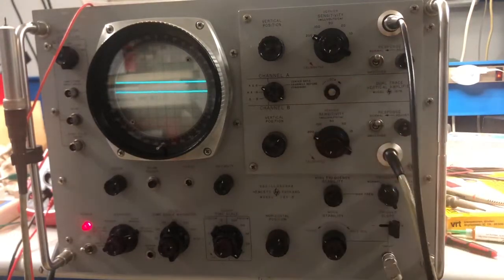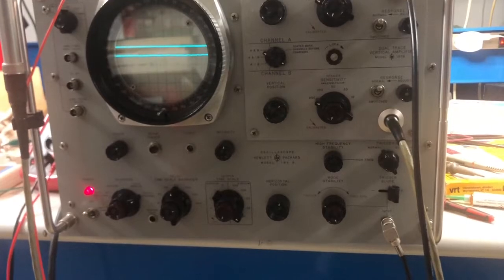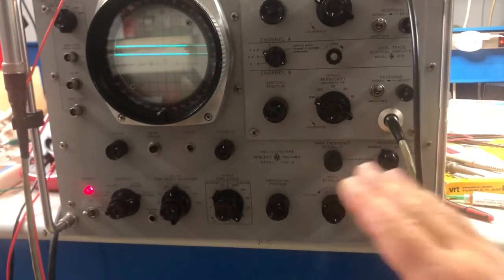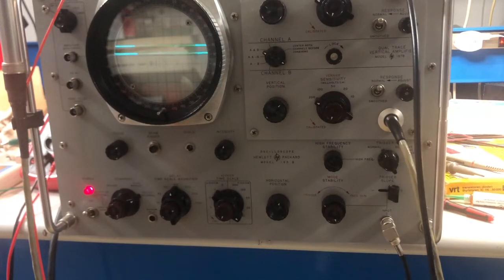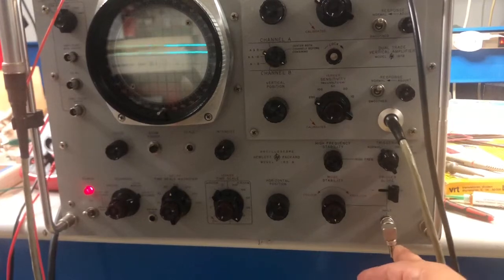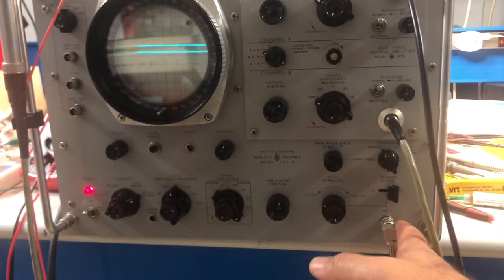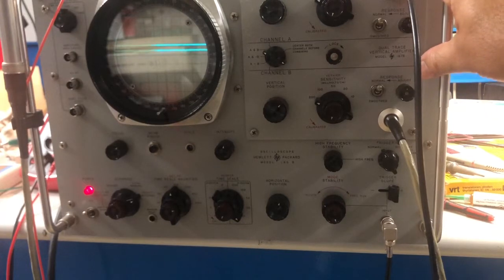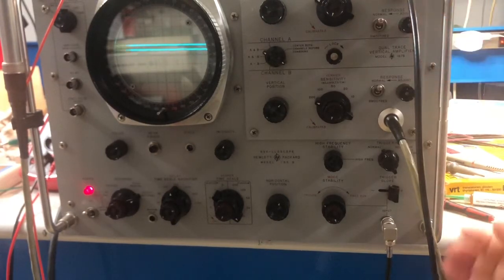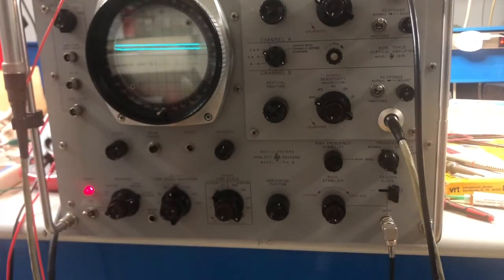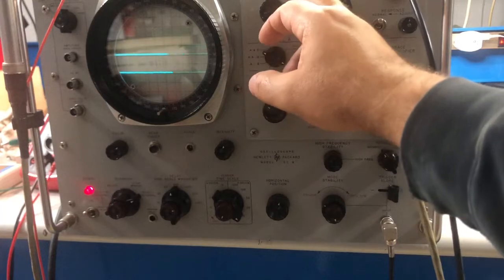Well, the way this oscilloscope works, it's not like a standard oscilloscope. This is a sampling oscilloscope, so the sampling rate should be synchronized with the signal. So it needs an input signal for triggering, and this signal should be related to the signal that we are going to monitor. In case you don't have such a triggering signal available, you can use a sync pulse that the oscilloscope produces to feed the unit under test and relate the output signal to that pulse. So this is the way it has been designed.